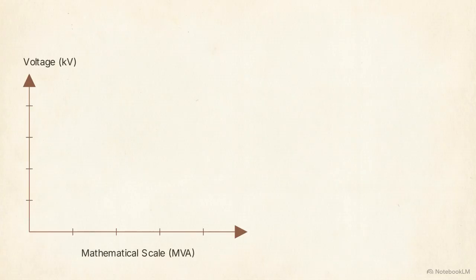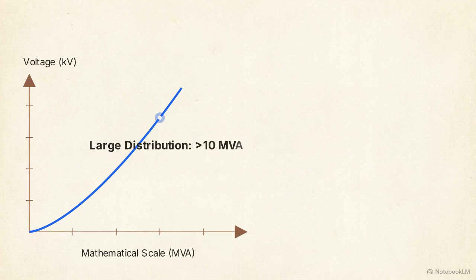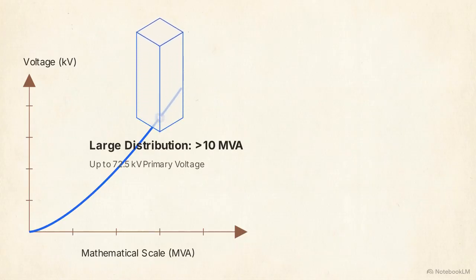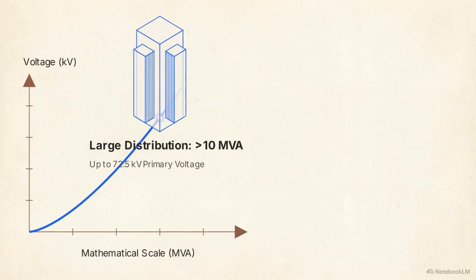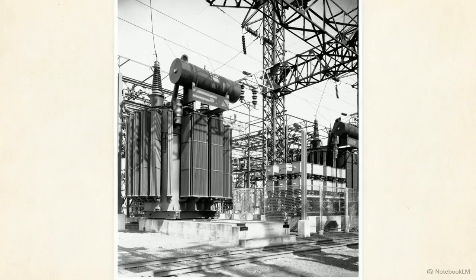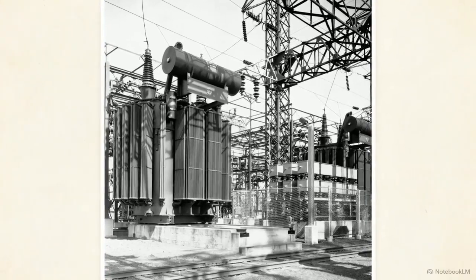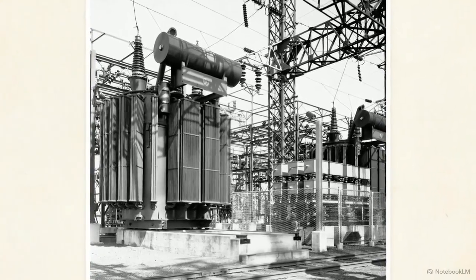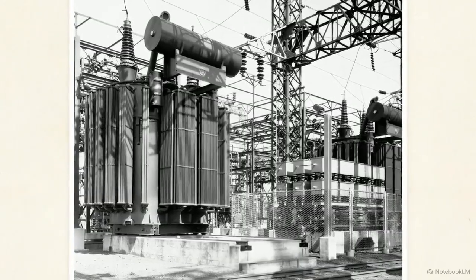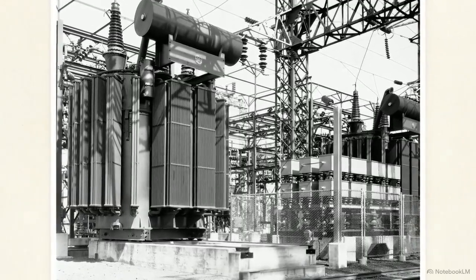To accurately categorize these machines, the taxonomy must be based strictly on their mathematical scale. This chart maps out a rating-based taxonomy beginning at the highest tier of the distribution network. The large distribution class handles extreme metrics, rated over 10 megavolt amperes, stepping down primary voltages of up to 72.5 kilovolts. Pushing that volume of power generates a severe thermal load. Cooling the dielectric fluid requires separate, massive external radiators bolted directly to the tank walls.